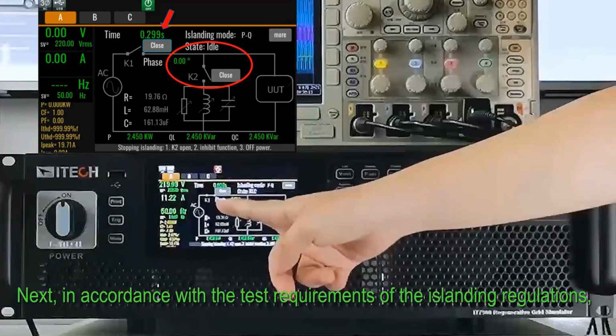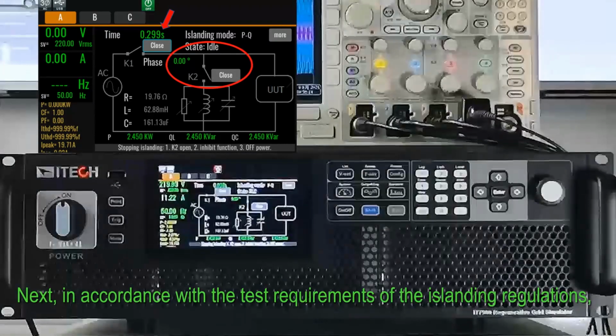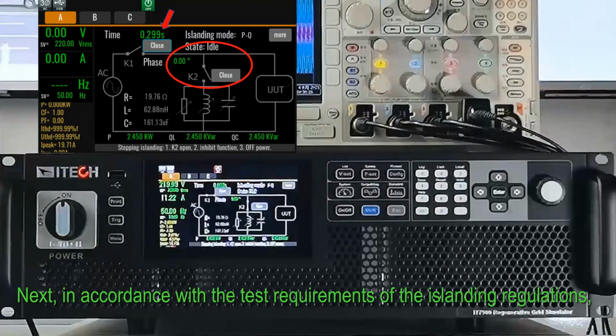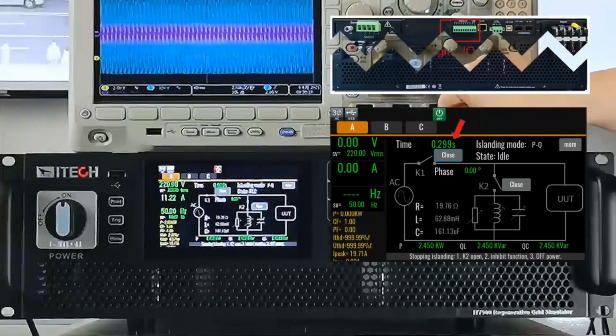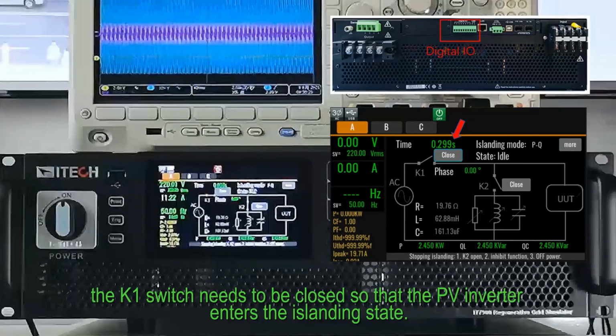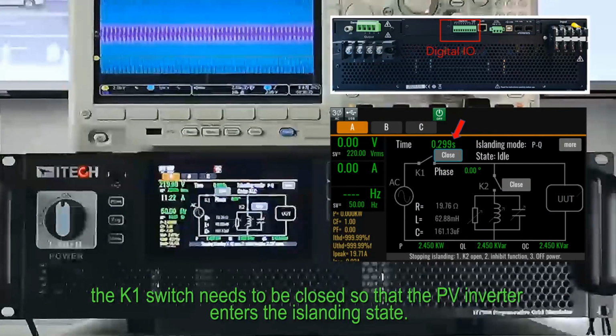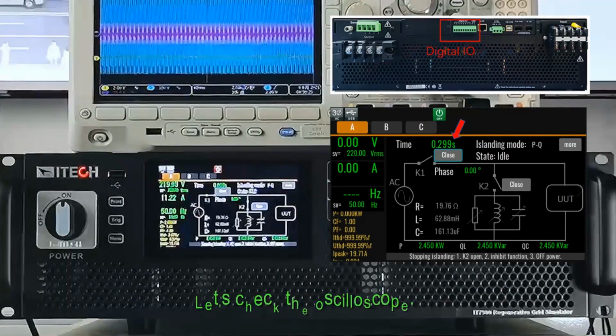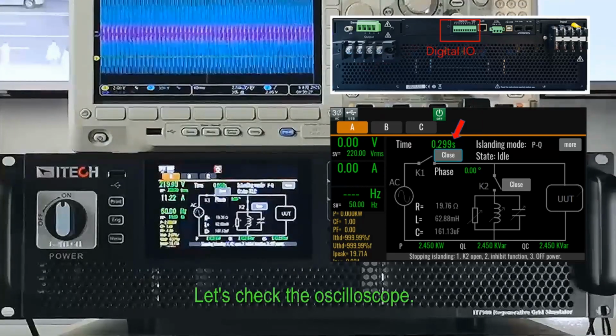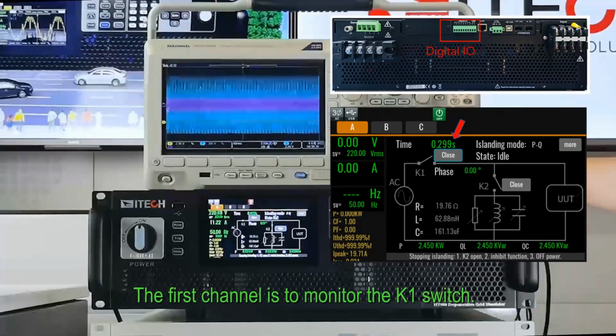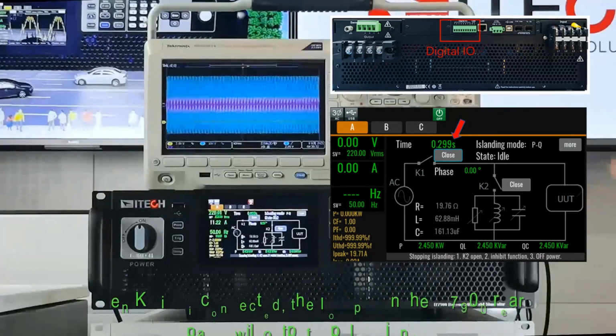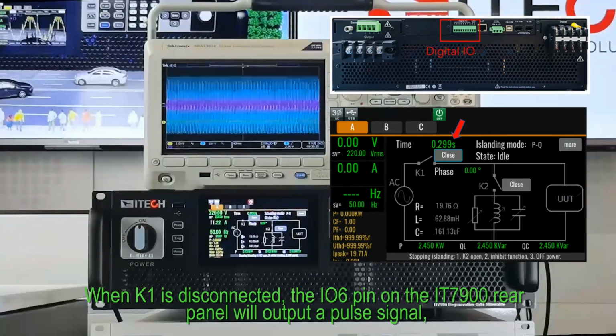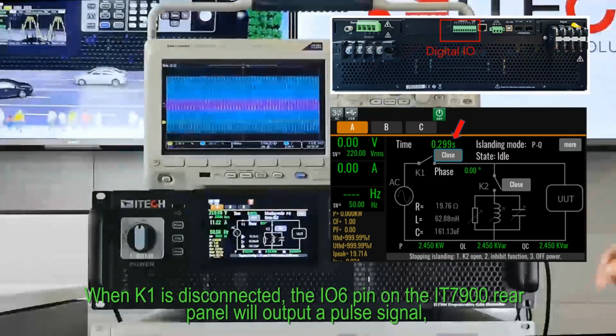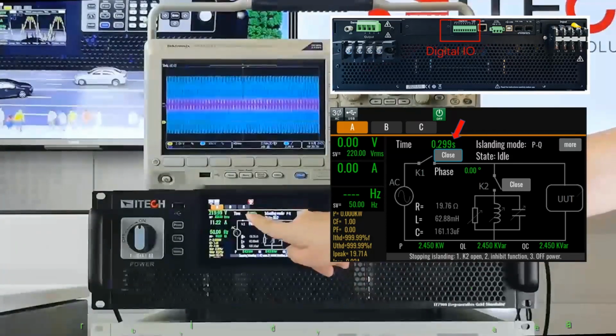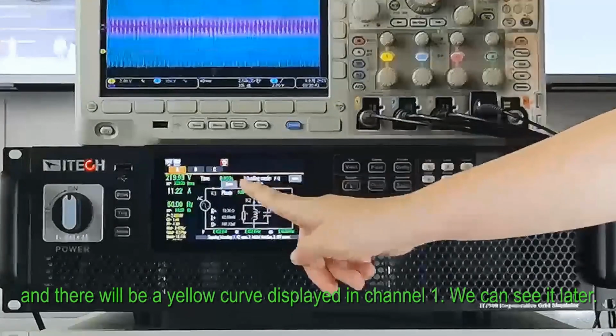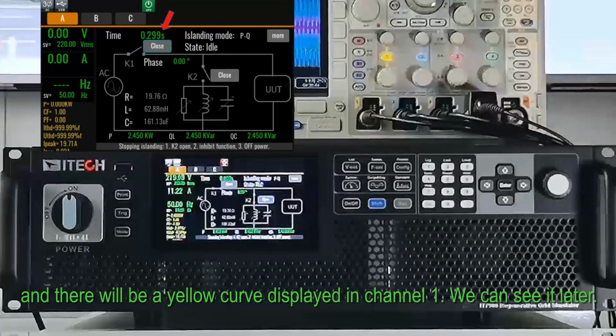Next, in accordance with the test requirements of the islanding regulations, the K1 switch needs to be opened so that the PV inverter enters the islanding state. Let's check the oscilloscope. The first channel is to monitor the K1 switch. When K1 is disconnected, the IO6 pin on the IT7900 rear panel will output a pulse signal, and there will be a yellow curve displayed in channel 1. We can see it later.